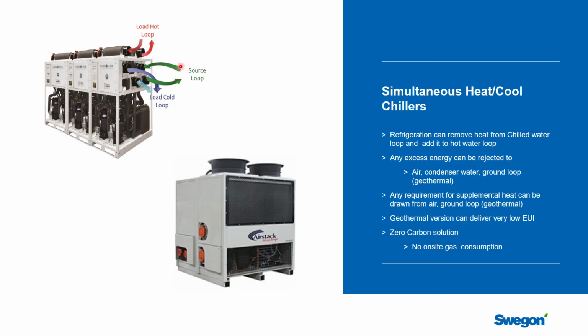This could also have been hooked to a cooling tower, and that heat could have been rejected. In the winter, you might find out that you're not putting enough heat into the system, and so we need a heat source. If this is geothermal, we would be warming this green loop up with the ground loop, and then the refrigeration plant would be raising its temperature from 35 or 40 degrees up to 110 degrees, so that we have a hot water source that we could use to do the heating in the building.